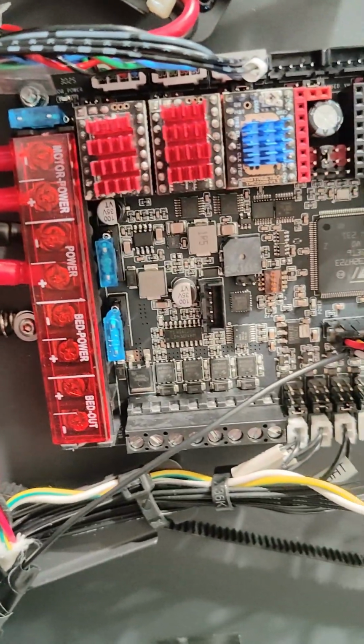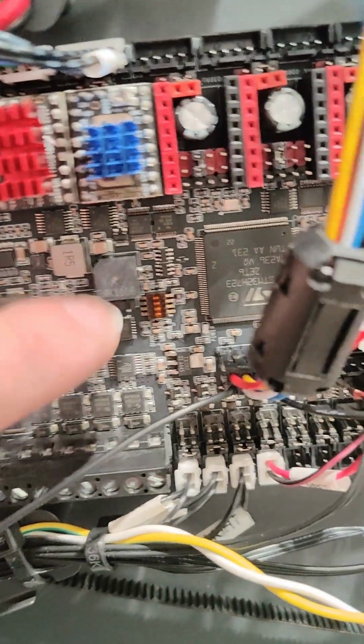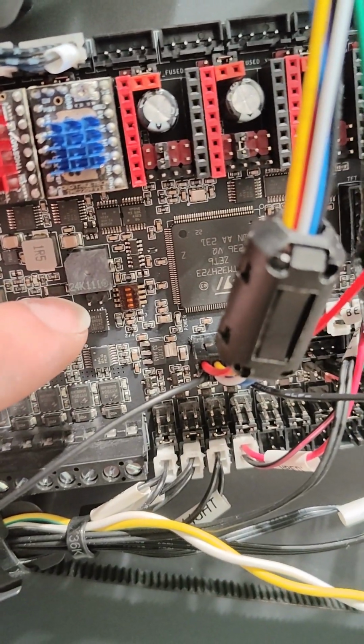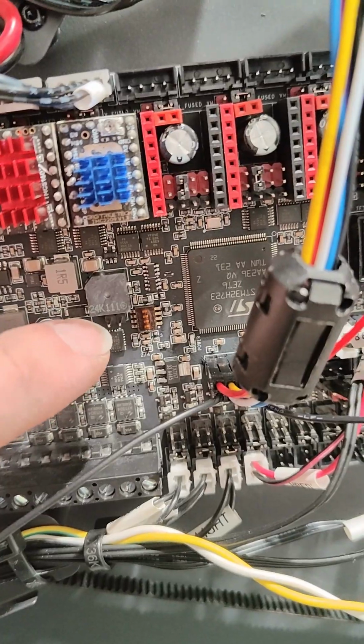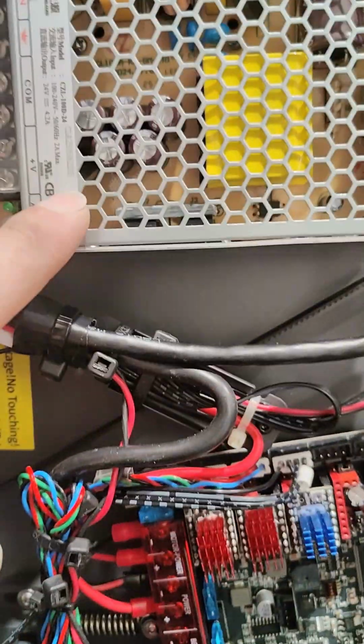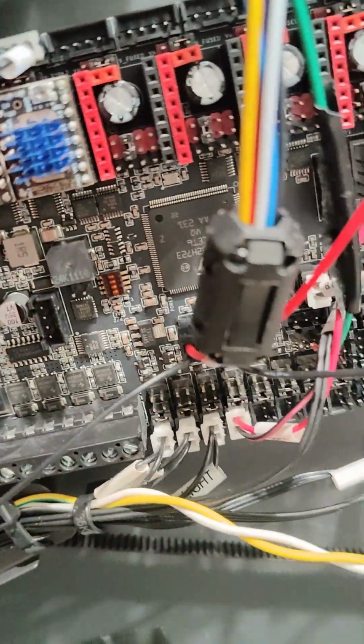And then all the jumpers, make sure all your jumpers are correct. That jumper should be out - this is the USB jumper. If that jumper's in and you're hooked up to your 24 volts or your 48, you'll burn everything out. So make sure you unplug that when you're done programming everything.